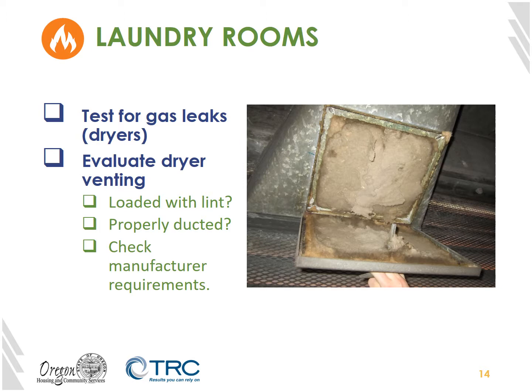This photo is an example of a real building that we went to, and this was the state of their existing dryer exhaust duct. I don't know where the dryer exhaust was going, but it certainly was not going out of this duct, which was clogged with lint for about 8 feet.